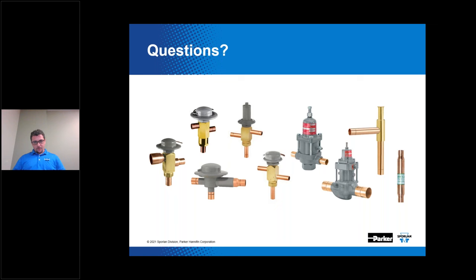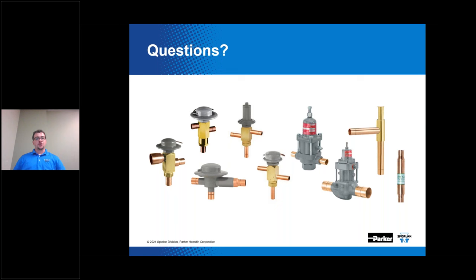Question: How could a field or maintenance technician measure the pressure drop across the TXV? What I would actually suggest is using our free online sizing software called Virtual Engineer on our website. You can punch in the exact operating conditions to see how much pressure drop you have across your distributor. Find your distributor model in the field, determine the pressure drop across the distributor, and backtrack to figure out the pressure drop across the expansion valve — because your combined pressure drop across the distributor and the expansion valve is knowable based on your high side pressure relative to your evaporator pressure.